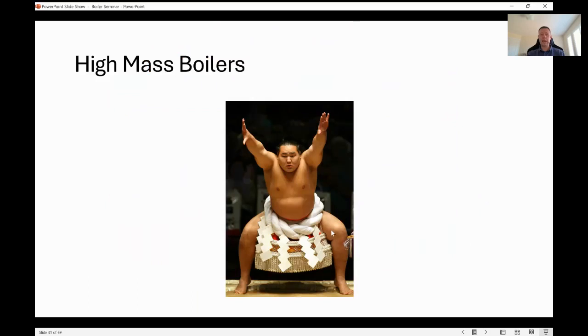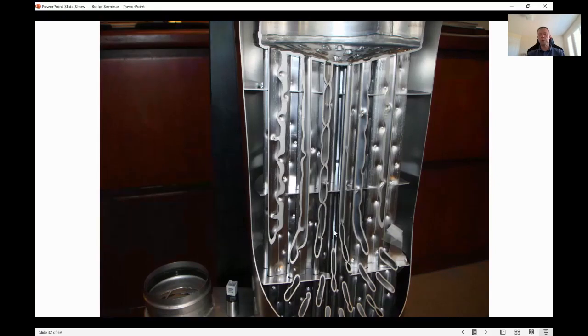So let's take a look at high mass boilers now. I said a high mass boiler, here's a heat exchanger for a high mass boiler. In a high mass boiler, you're going to have the flue products through the tube and you're going to be surrounded by a larger mass of water. Each of these tubes will have dimples on it. Those dimples are creating turbulence in the flue products, so you're maximizing the heat transfer you're getting out of it.